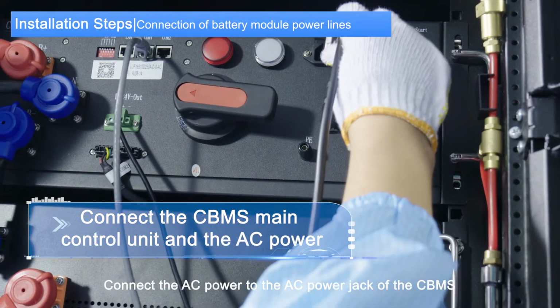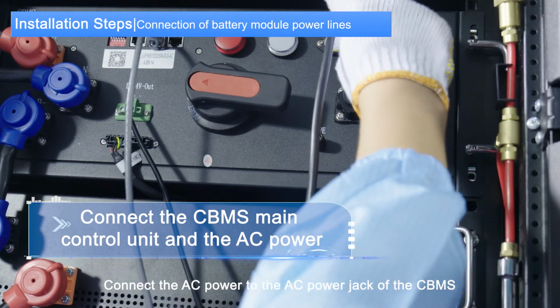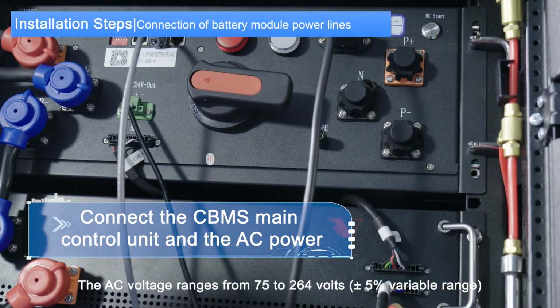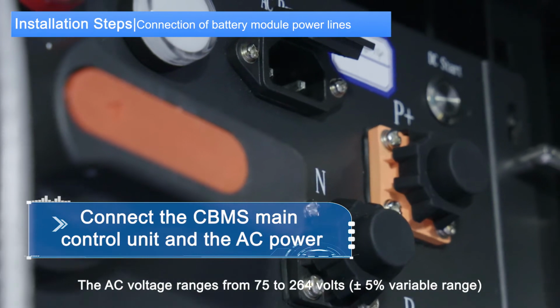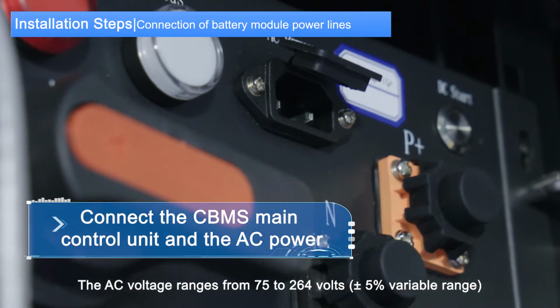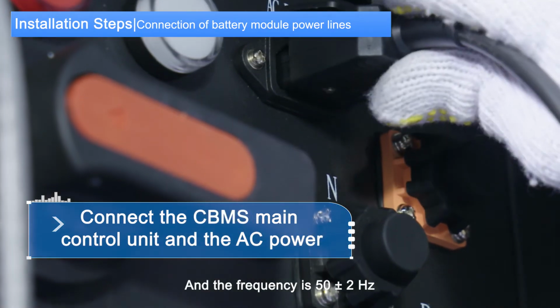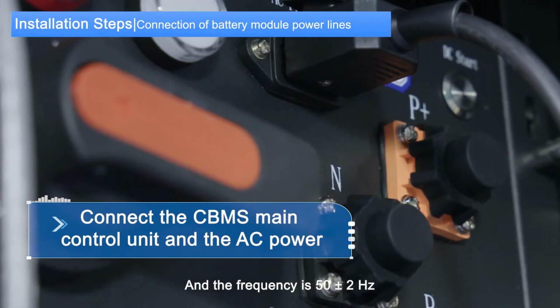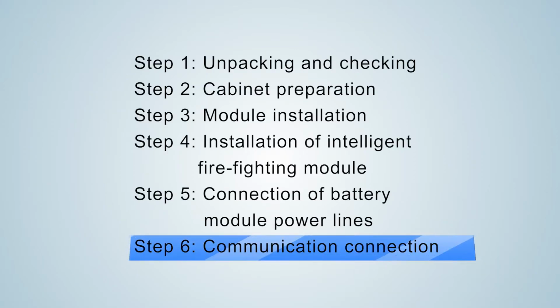Connect the AC power to the AC power jack of the CBMS. The AC voltage ranges from 75 to 264 volts, positive and negative variable range, and the frequency is 50, positive and negative 2 Hz. Step 6. Communication connection. 1.